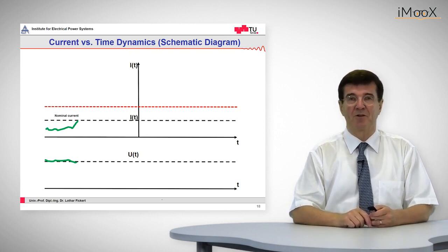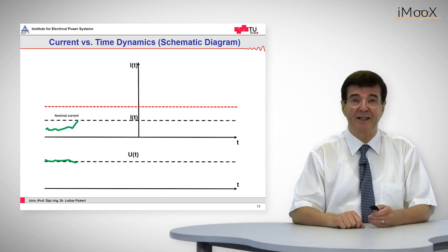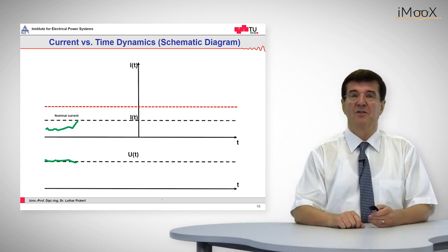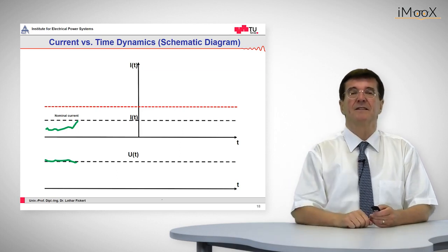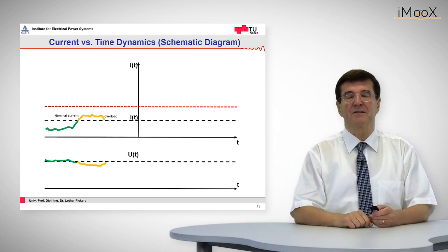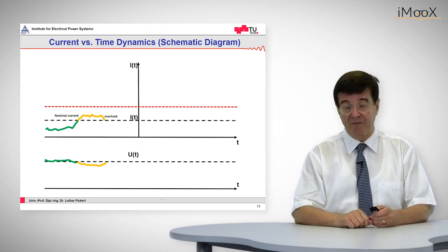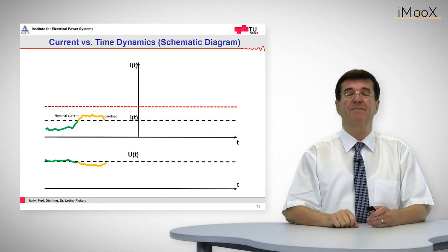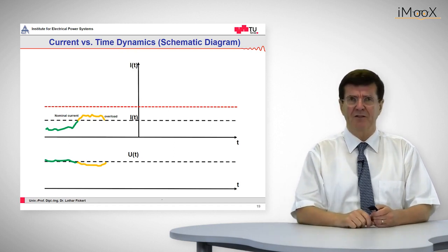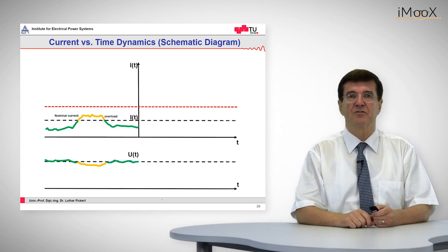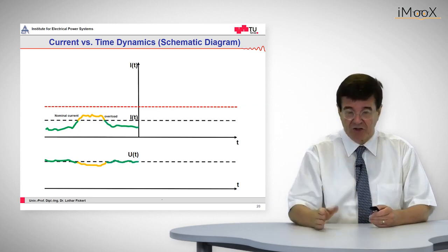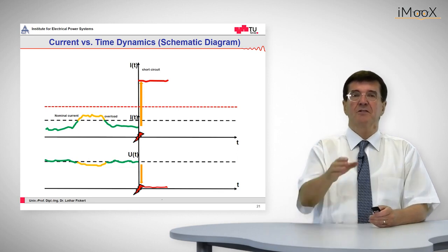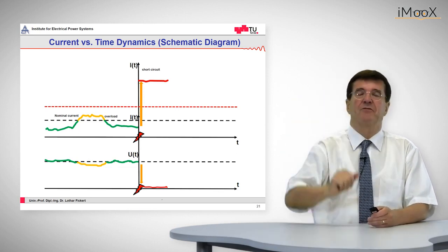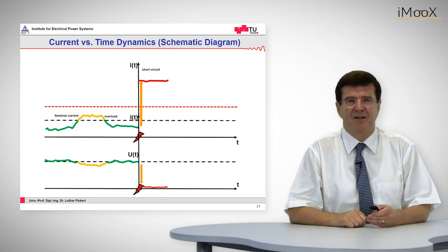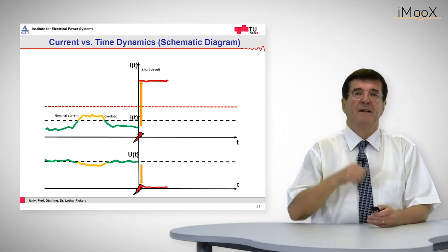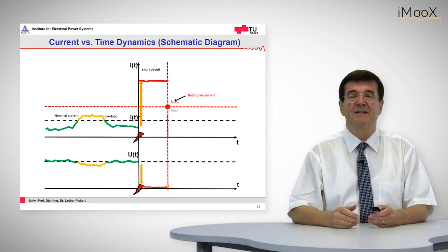First we start again with the normal operation. Everything is in the so-called green range. The voltages are more or less okay and the current is below its nominal value. If the current of this means of electricity transport goes above the nominal value, which is given by the dotted line, then we speak about overload, and at a certain time it will go back to normal operation. And now this short circuit occurs. What does it mean? The voltage breaks down and the current goes up to values of some typical kiloamps, for example, 5 kiloamps. The current goes on and on until the protection comes in.